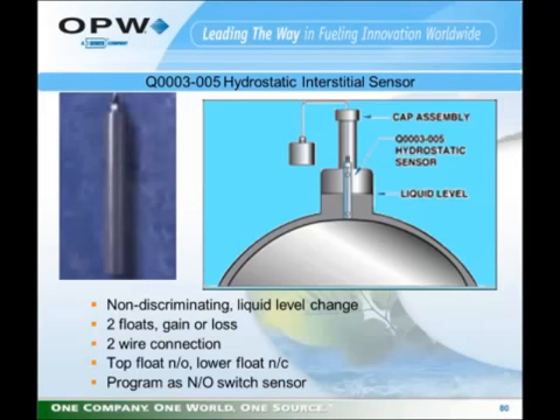The Q0003-005 hydrostatic interstitial sensor. This is for a reservoir sensor for a double wall tank that has a brine or other solution between the walls of the tanks. It's a non-discriminating liquid level change sensor. It has two floats and is normally installed so that the normal fluid level is between the two floats. As the liquid goes up, it would activate the upper float. As it goes down, it would activate the lower float and generate an alarm at the gauge. It's programmed as a normally open switch sensor.